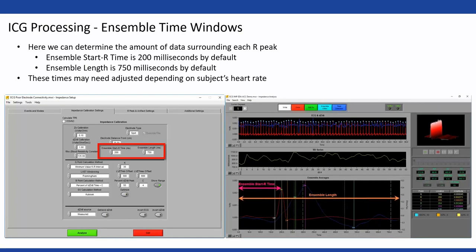For ensemble time windows, we're looking at how much data surrounds each R-peak. Normally we set this to a default value of 200 milliseconds for the start, and the ensemble length is 750 milliseconds. As you can see in the picture, the ensemble start time and length are shown. You'd normally leave these at defaults. The only reason to adjust them is if you're studying someone with a very fast heart rate, but most of the time these are fine as they are.